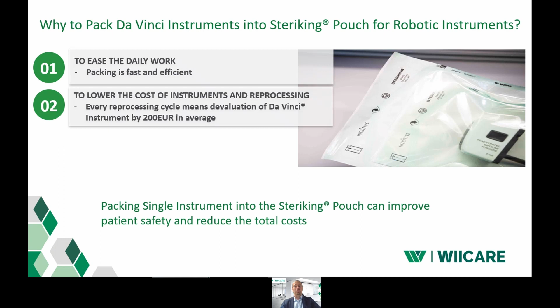Third very good reason to use pouches is to improve the patient safety, and that happens in many different ways. The material, as Tommy was telling, is very strong, and you will not have compromises with the sterility very easily with this. Another reason why this is safer is that when you are using the sealing machine, you can do it repeatedly always, and it's a validatable process. So the closing is always happening the same way. And altogether, when you are packing the single instruments, it's easier to make sure that you are reprocessing these instruments only the amount of times that are allowed by the instructions for use.